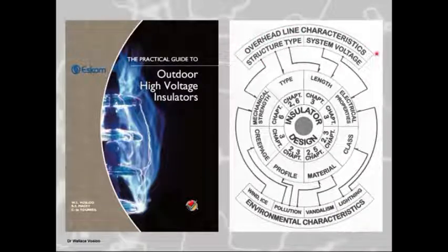Overhead line characteristics. Normally you'll find there's a structure type you're going to select, and that structure type is going to determine the mechanical strength of the insulator, which is in chapter 6. There's a whole chapter on the strength. The structure type is also going to determine the type of insulator. Is it going to be a long rod insulator? Is it going to be a post insulator? Or what type of insulator is it going to be? And that normally influences the length of the insulator.